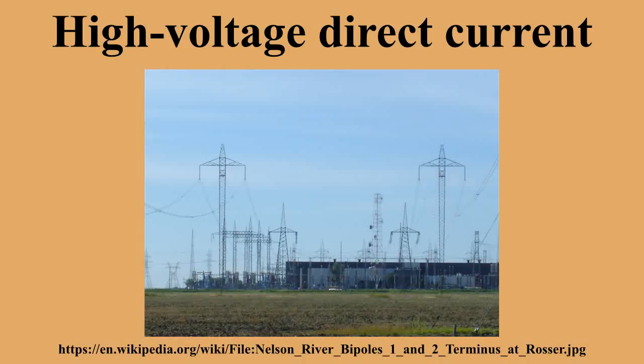Asynchronous connections. Because HVDC allows power transmission between unsynchronized AC distribution systems, it can help increase system stability by preventing cascading failures from propagating from one part of a wider power transmission grid to another. Changes in load that would cause portions of an AC network to become unsynchronized and to separate would not similarly affect a DC link, and the power flow through the DC link would tend to stabilize the AC network.